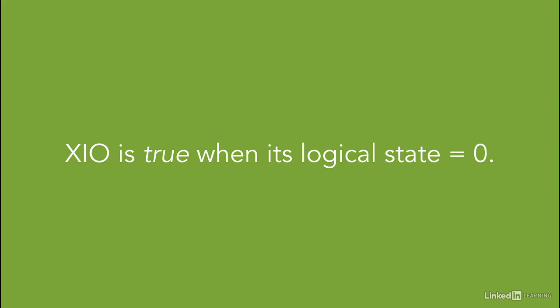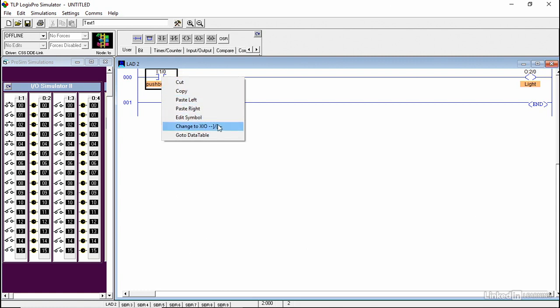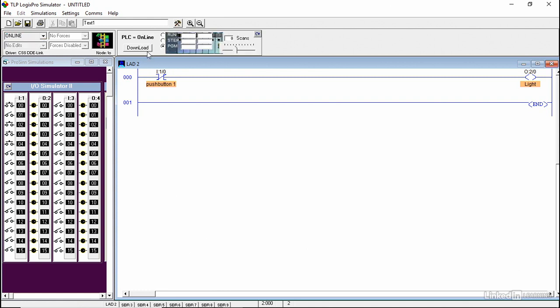Let's use the simulation software to see how the program behaves when using XIO instruction. We are using the same wiring and connection — the only thing we need to change is the instruction. There are two methods: you either right-click on the instruction and change it to XIO, or drag the instruction from the instruction panel. We go online, download the program, and click run mode. Notice that without even pressing the push button, the light is on. As soon as we press the push button, the memory location changes to 1, the instruction is not activated, and as a result, the light turns off.